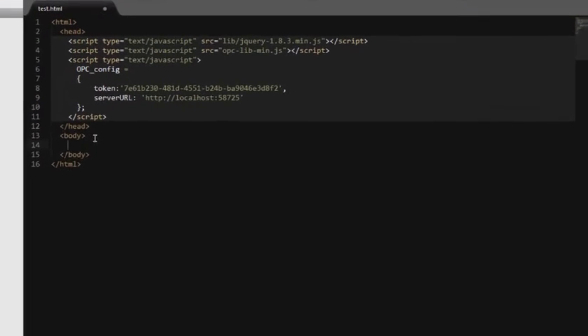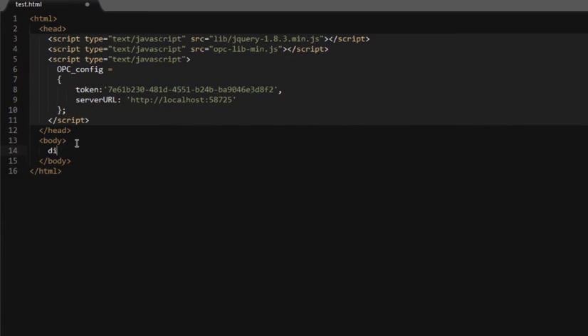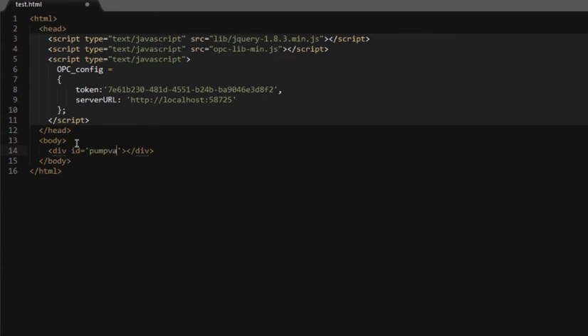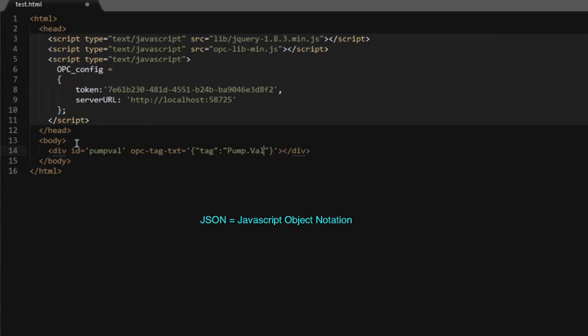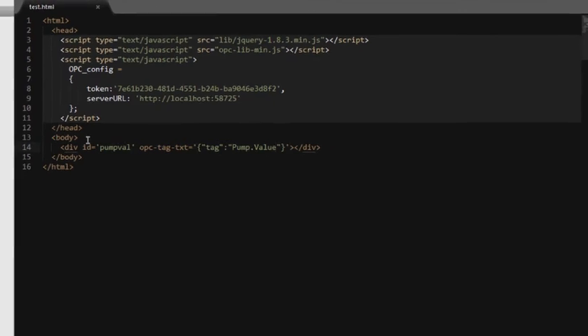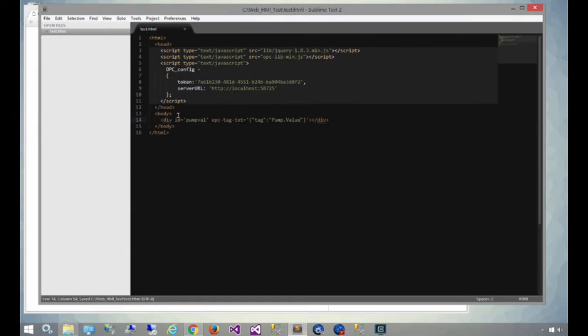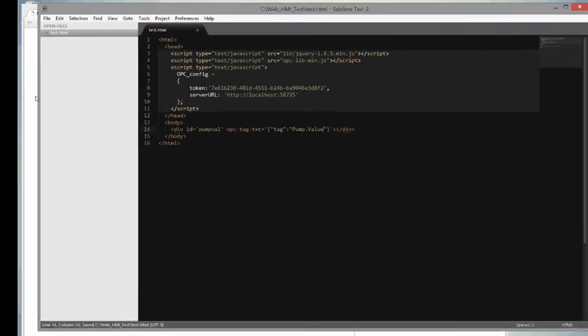We're going to add in a couple of items. The first is going to be a div and it's going to be bound to the pump value that we looked at in the configure tags application. We'll put in a special attribute called opc tag text. This is going to control the text and bind to the text property of this div. We're going to set up tag and pump value. You'll see this is JSON formatted. With that simple attribute, we just refresh the page and that binds directly to the pump.value on the server.